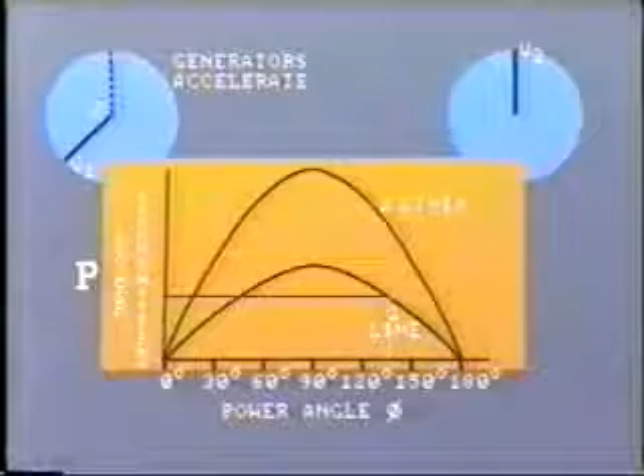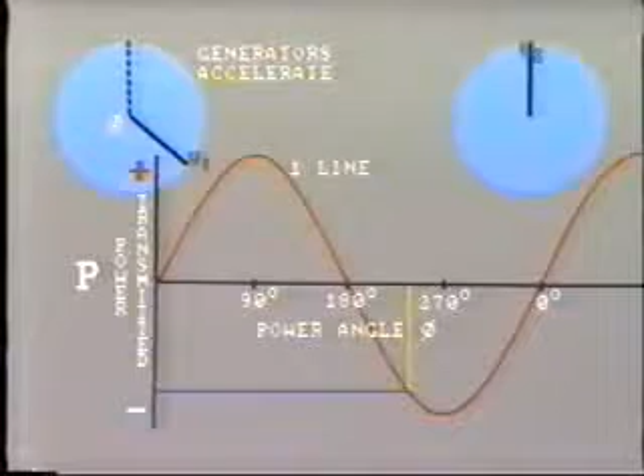When the rotor passes the 180-degree mark, it's now approaching V2 again, so it can be considered to be lagging. It is trying to catch up to V2. But look what's happening to the power curve. Once the voltage displacement goes beyond 180 degrees, the power flow along the line reverses. Bus 2 is now feeding bus 1. The power flow in this direction is trying to assist the generator rotor at bus 1 to catch up. This is instability.